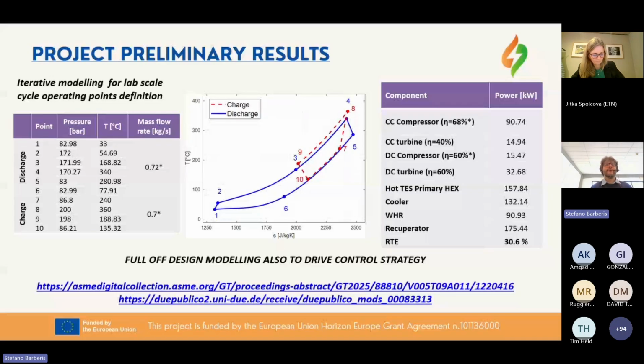We are going to an RTE that is between 20 and 30% at the end of the day for this cycle at laboratory scale. But it's true that if we would be able, particularly for upscale solutions, to increase the efficiency of the different machines, think about the turbine or the volumetric compressor, as well as increase the temperature of the storage, most probably this RTE efficiency, as we already checked with some simulation, can achieve around 0.5, 0.6.